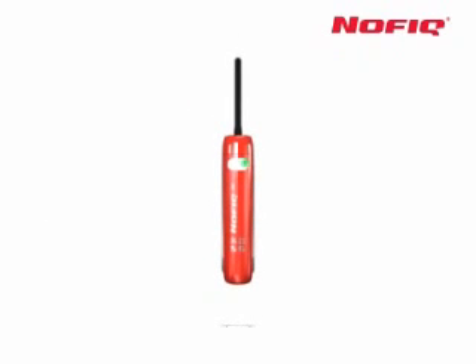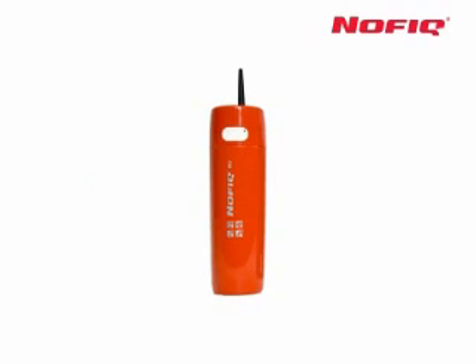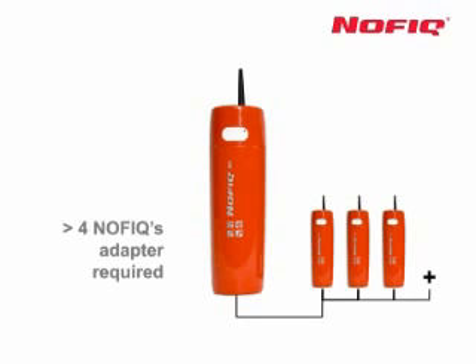Depending on the size of your switchbox, NOFIQ comes in two varieties: the NOFIQ 20 for a volume of 0.25 cubic meters and the NOFIQ 80 for a volume of 0.9 cubic meters. For larger switchbox volumes, NOFIQ can link up multiple units to work as a single system, protecting switchbox volumes of up to 6 cubic meters.